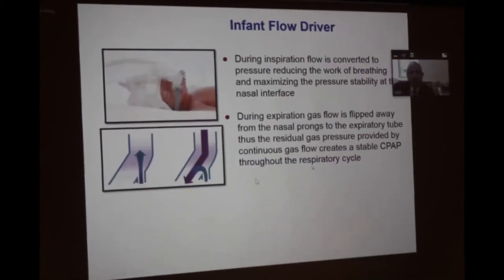To illustrate further, in the variable flow infant flow driver, during inspiration the flow is converted to pressure. It reduces the work of breathing and maximizes pressure stability at the nasal interface. However, during expiration, the flow is flipped away from the nasal prongs to the expiratory tube. Thus, the residual gas pressure provided by the continuous gas flow creates stable CPAP pressure during the whole respiratory cycle.